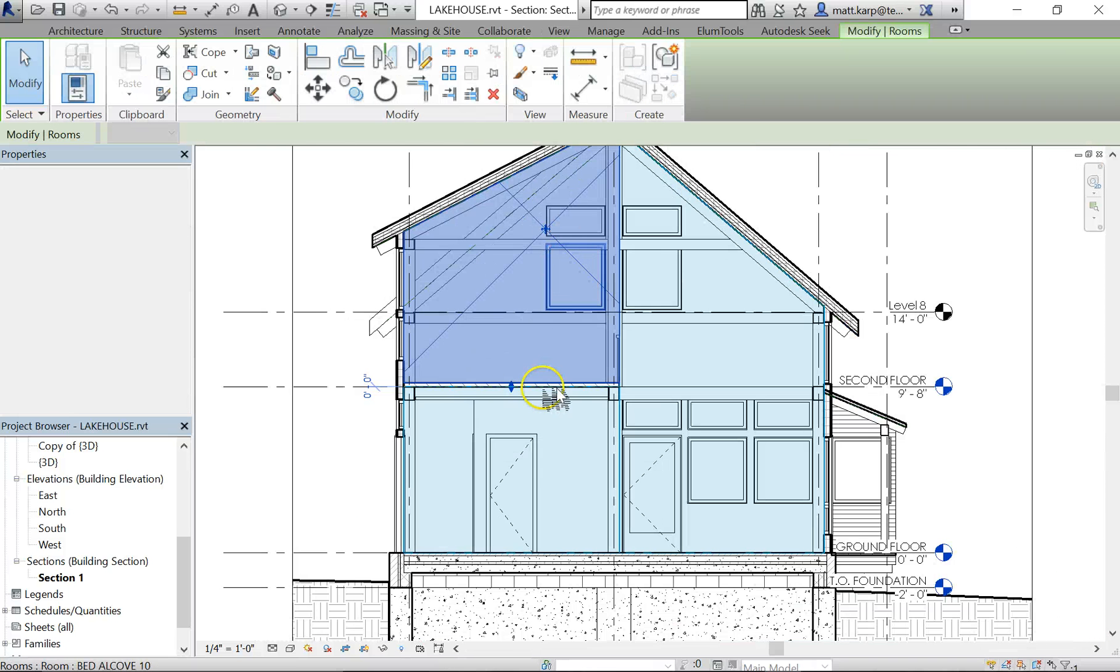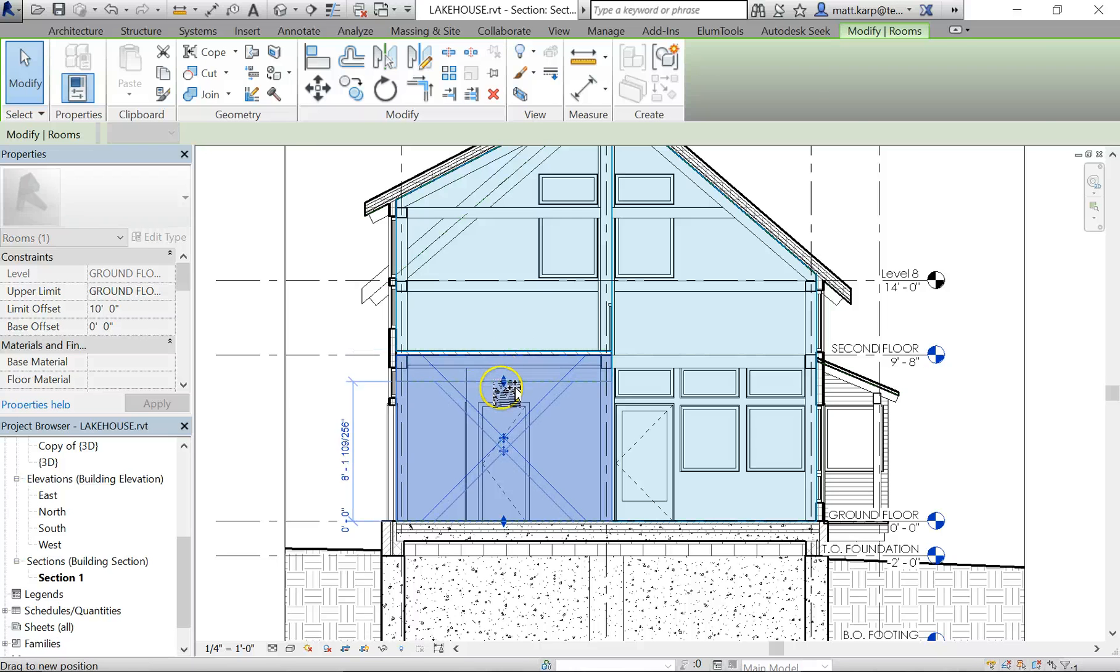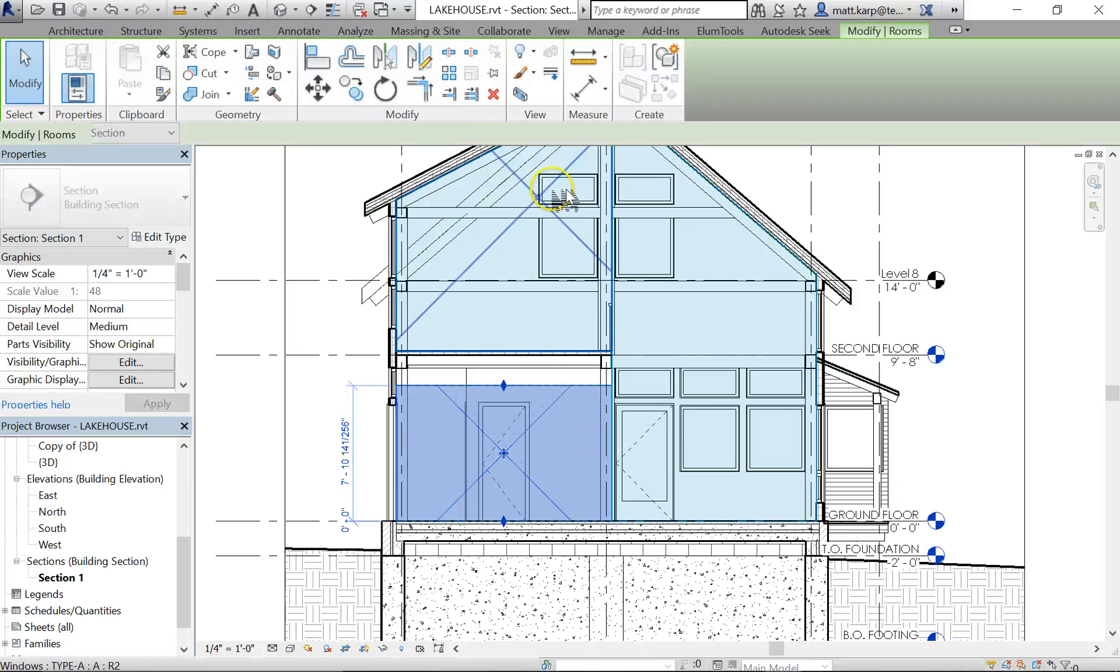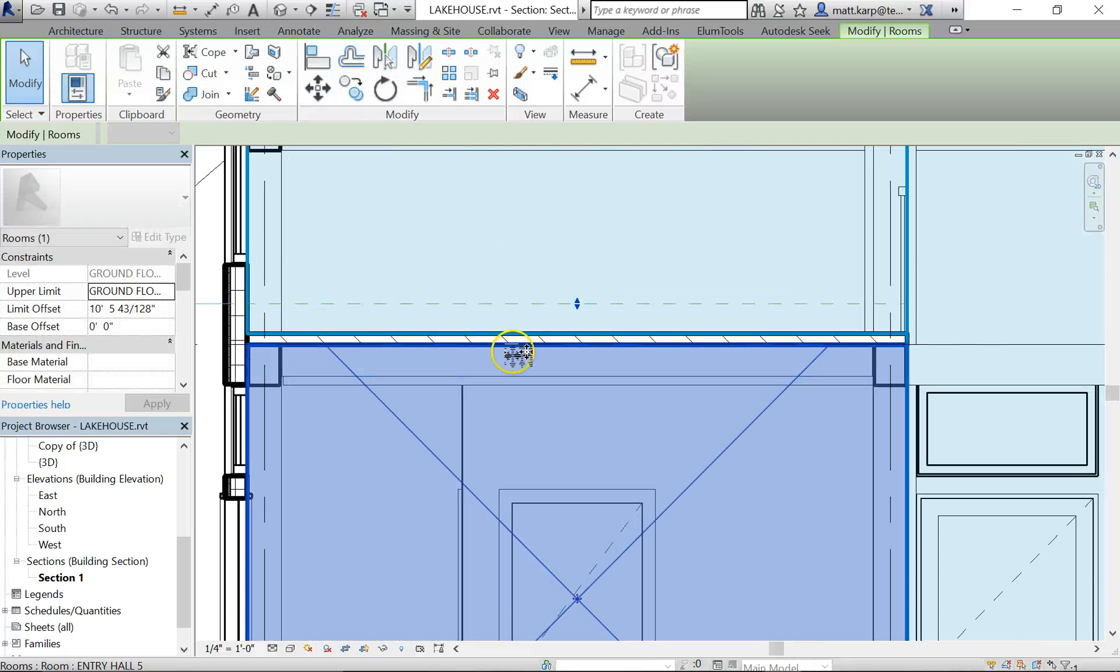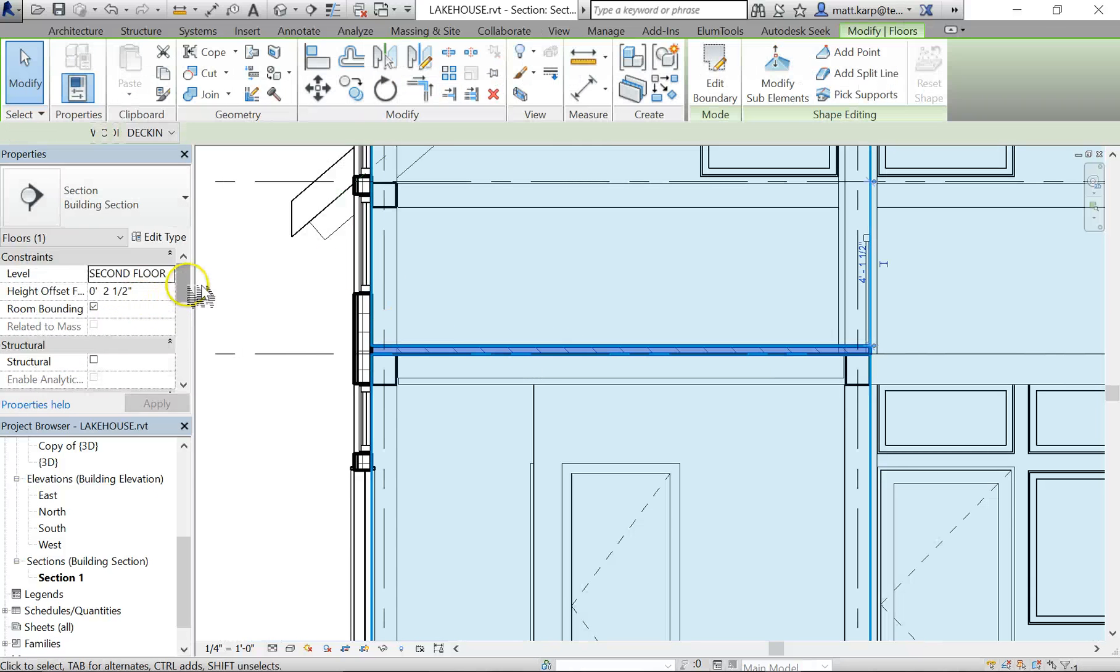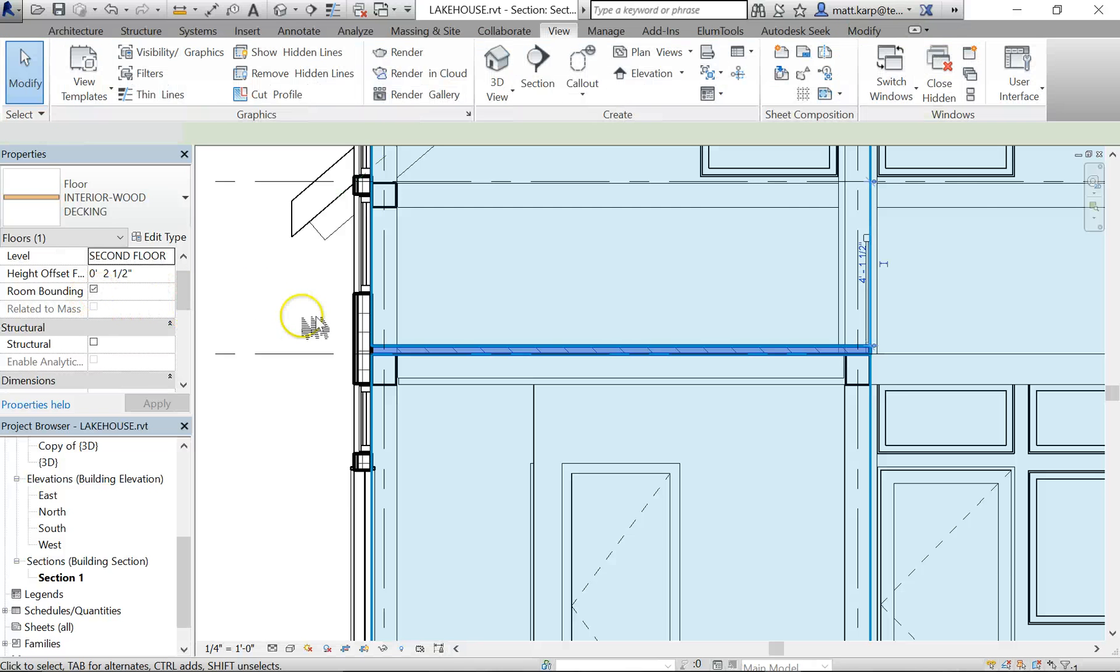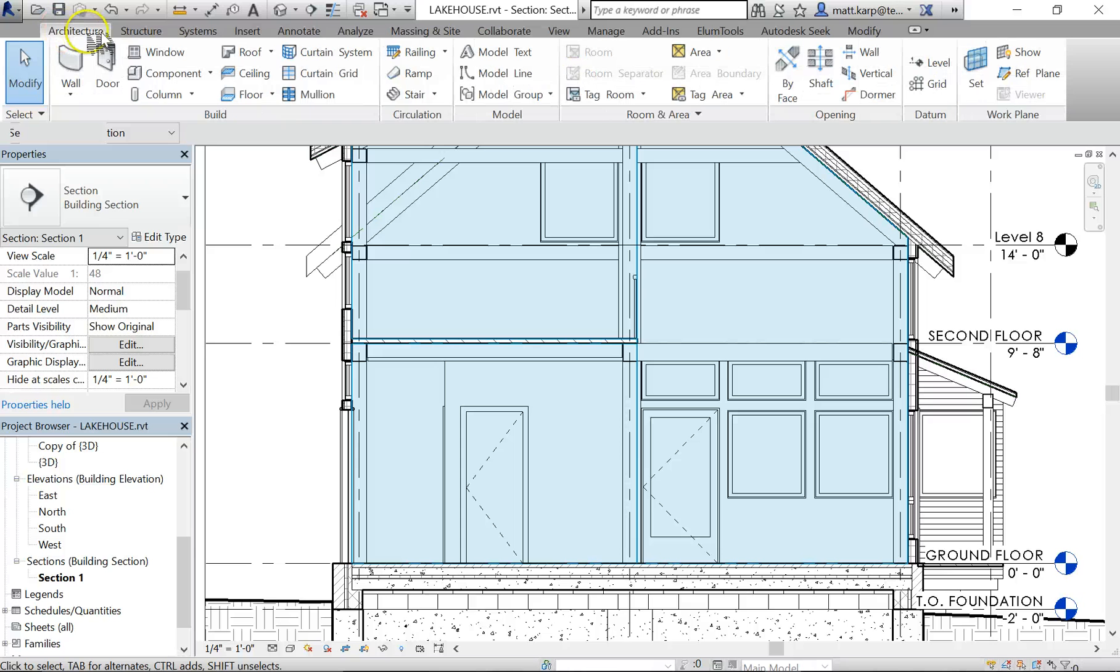What this does is typically when you place a room, I'll show you what it normally is. You typically place a room and it's probably going to be like that, and that's a problem when you're running tests on the analysis. If you find any rooms like that, as long as you have area and volume turned on, you can pull them up. It won't go into this room because it's stopping at this floor because that floor is room bounding. Same thing with walls. If you ever find a room stopping at a place where you don't think it should be stopping, the only things that would stop it are anything that is a room bounding element such as a floor, wall, or roof, or a room separating line.